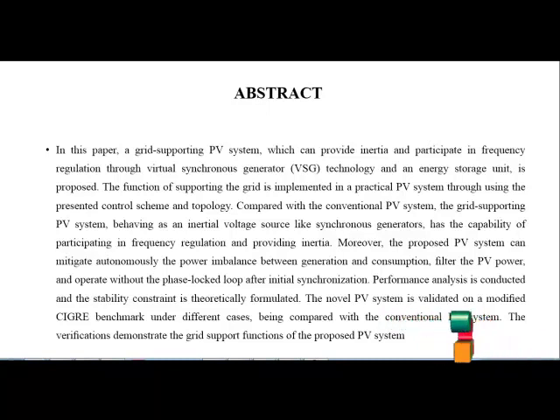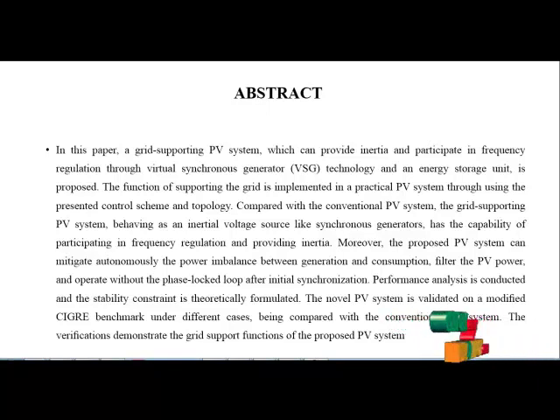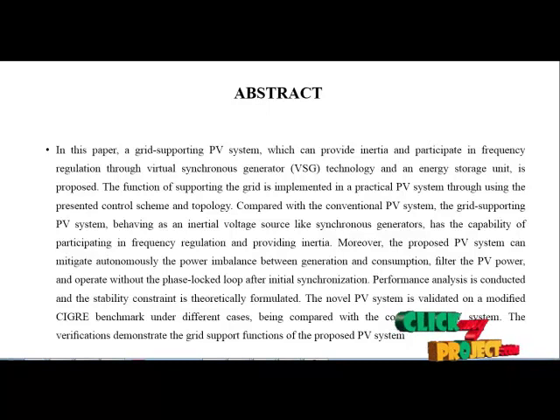Comparing the conventional PV system and grid-supporting PV system: the proposed system behaves like an inertial voltage source similar to a synchronous generator, with the capability of frequency regulation and providing inertia. The proposed PV system automatically mitigates power imbalance between generation and consumption, filters the PV panel output, and operates without a phase-locked loop after initial synchronization. The performance analysis of connecting and stabilizing the system is theoretically formulated, validated on a modified benchmark under different cases compared with the conventional PV system.